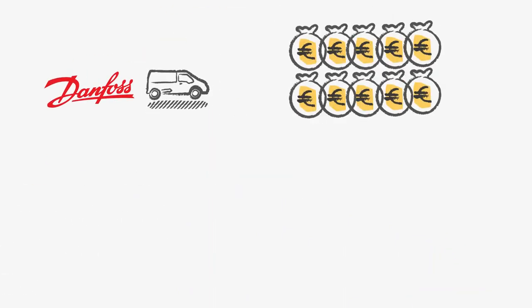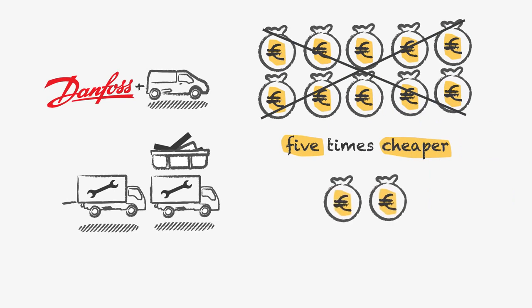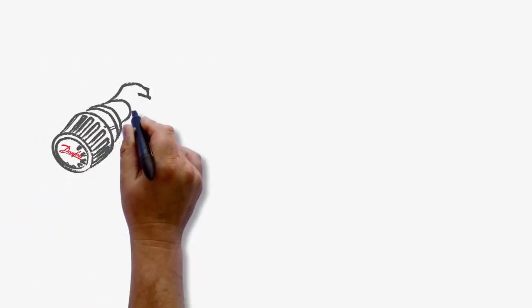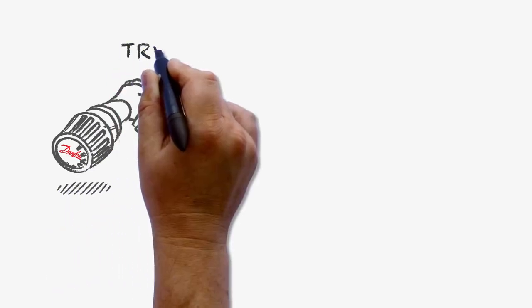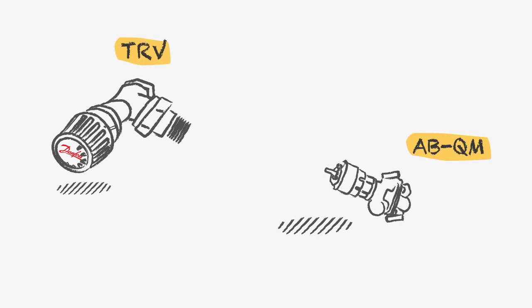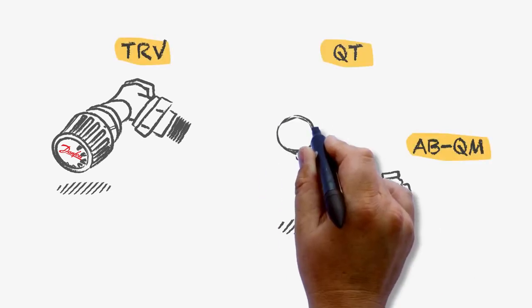And the good news is that the investment is about five times cheaper than a renovation to a completely new two-pipe system. All you need is a thermostatic radiator valve, an ABQM pressure-independent balancing valve, and a thermostatic controller.